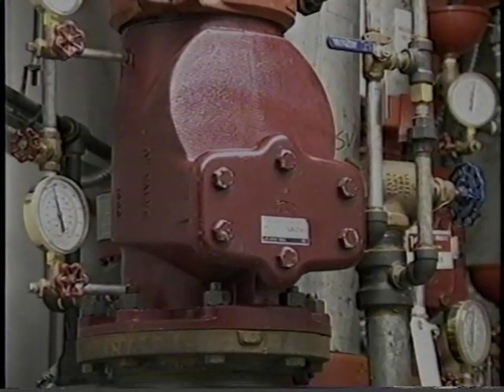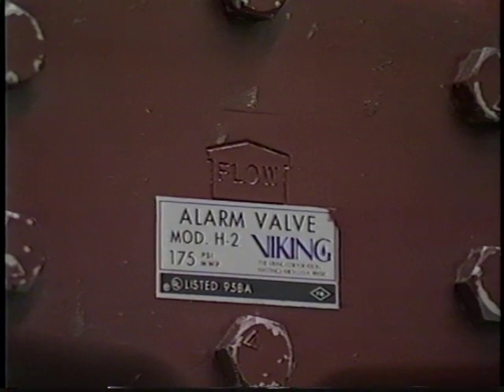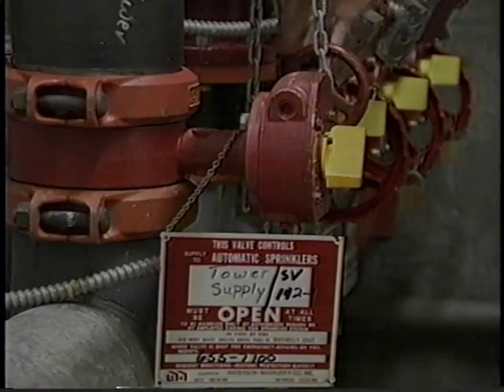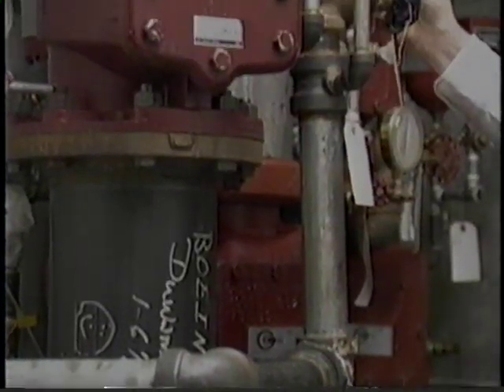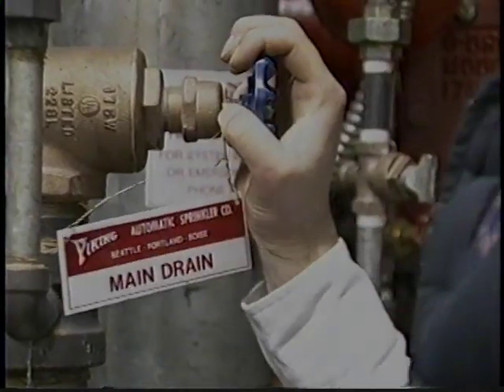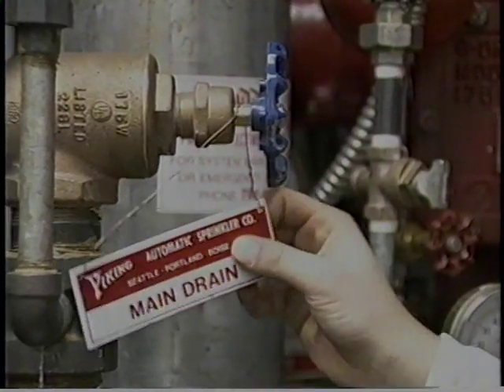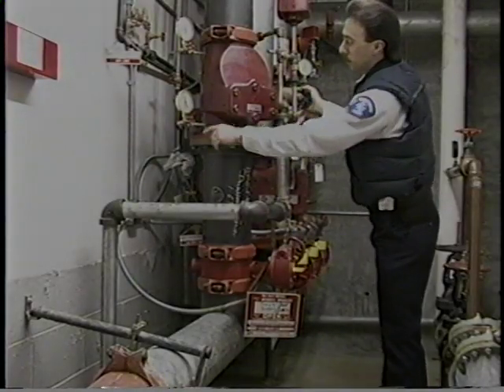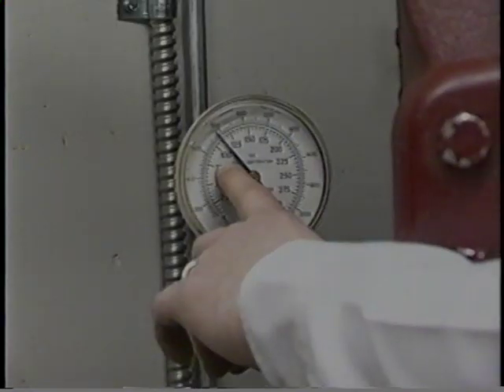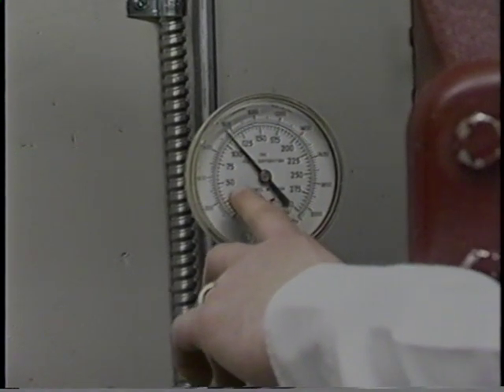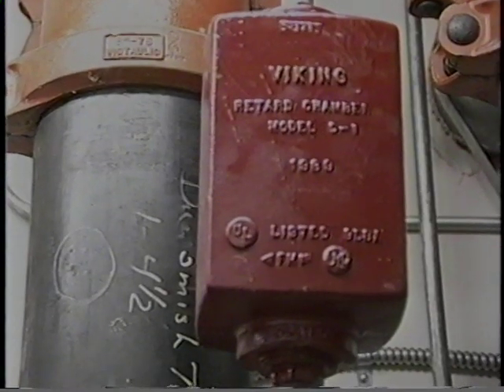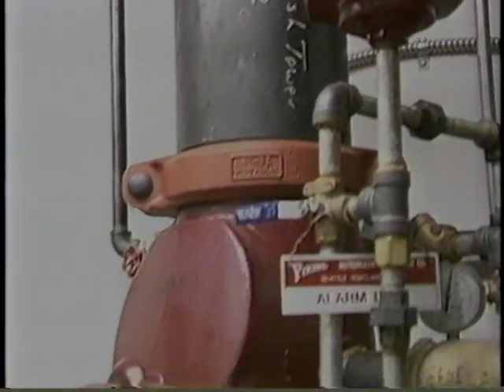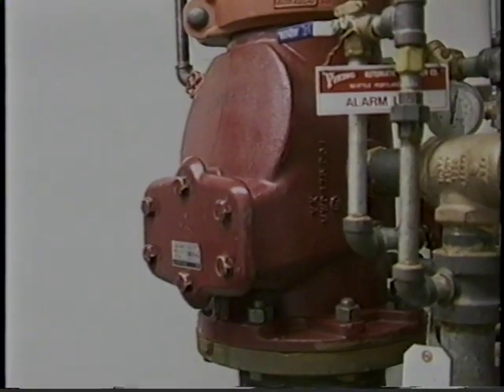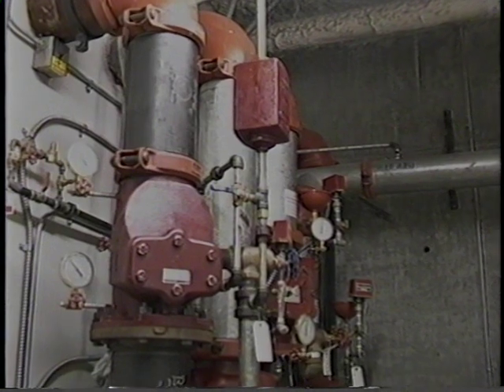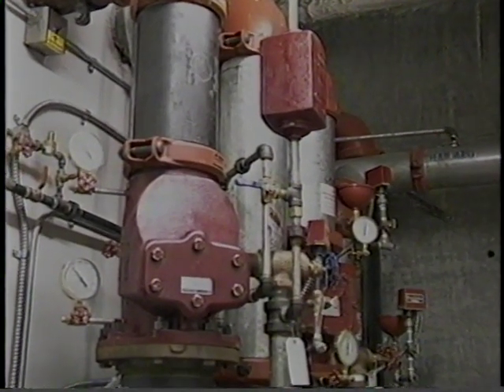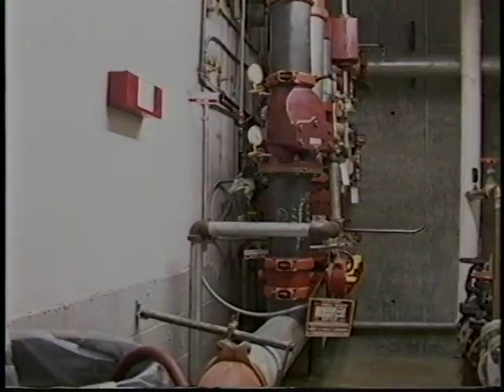Wet pipe systems usually have an alarm check valve installed in the main riser. To shut down the system, turn off the main water control valve and open the main drain. A pressure gauge on the riser should indicate when there is no longer any water pressure in the system. A wet pipe system may have a device known as a retard chamber in the alarm check valve. The retard chamber reduces false alarms by catching excess water that may go through the alarm valve during brief surges in water pressure.